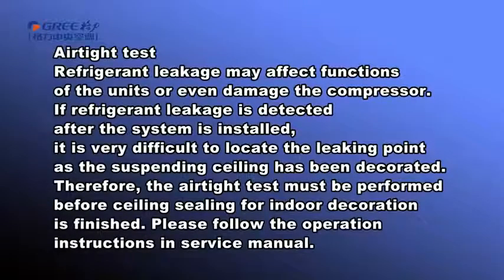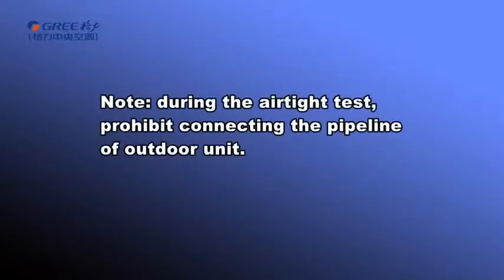6th, airtight test. Refrigerant leakage may affect functions of the units or even damage the compressor. If refrigerant leakage is detected after the system is installed, it is very difficult to locate the leaking point as the suspending ceiling has been decorated. Therefore, the airtight test must be performed before ceiling for indoor decoration is finished. Please follow the operation instructions in the service manual. Note, during the airtight test, prohibit connecting the pipeline of outdoor unit.